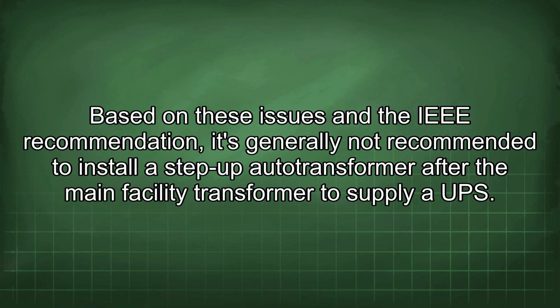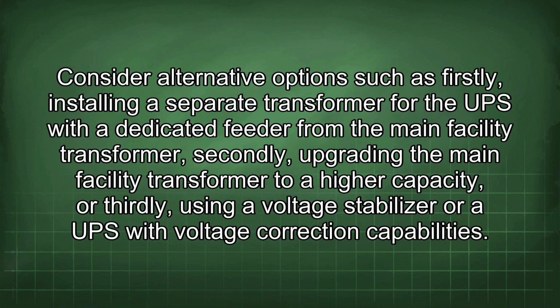Based on these issues and the IEEE recommendation, it's generally not recommended to install a step-up autotransformer after the main facility transformer to supply a UPS. Consider alternative options such as, firstly, installing a separate transformer for the UPS with a dedicated feeder from the main facility transformer; secondly, upgrading the main facility transformer to a higher capacity; or thirdly, using a voltage stabilizer or a UPS with voltage correction capabilities.